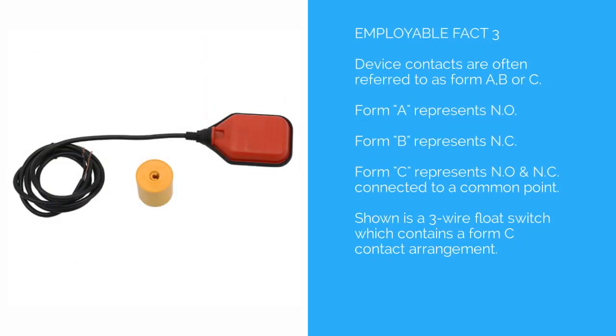Employable Fact 3: device contacts are often referred to as Form A, B, or C. Form A represents normally open. Form B represents normally closed. Form C represents normally open and normally closed connected to a common point. Shown is a 3-wire float switch which contains a Form C contact arrangement.